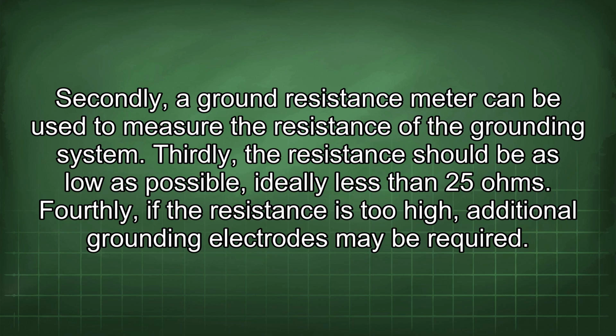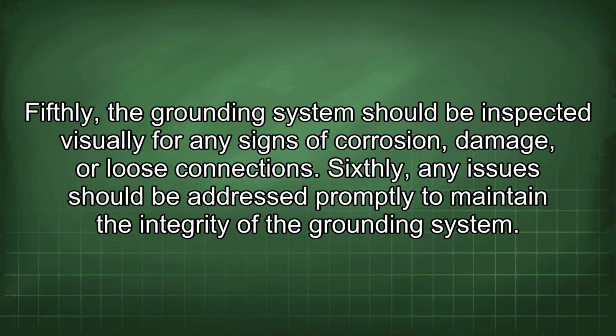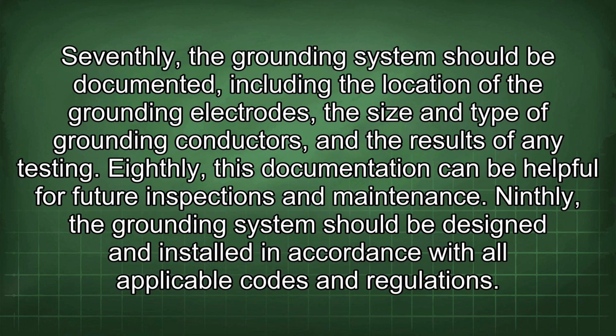Thirdly, the resistance should be as low as possible, ideally less than 25 ohms. Fourthly, if the resistance is too high, additional grounding electrodes may be required. Fifthly, the grounding system should be inspected visually for any signs of corrosion, damage, or loose connections. Sixthly, any issues should be addressed promptly to maintain the integrity of the grounding system. Seventhly, the grounding system should be documented, including the location of the grounding electrodes, the size and type of grounding conductors, and the results of any testing.